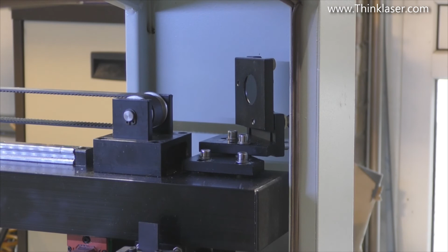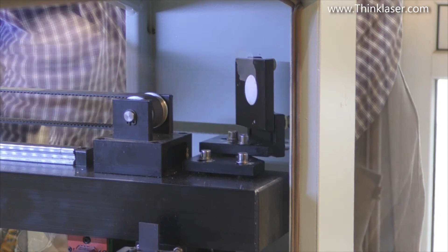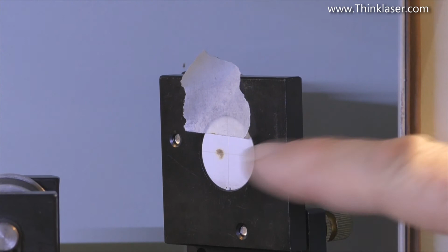Okay, so we've driven mirror 2 right to the front edge of the machine. We'll put a target into mirror 2. Well, we can see that it's quite a long way out on mirror 2. Height is not bad. This mark is what I call a sighting mark. So what I'm going to do is to tip mirror 1 very slightly. Okay, now that's not far out. It does not have to be perfect. It has to be more or less on centre. But, you know, 1 millimeter either way is not a problem.